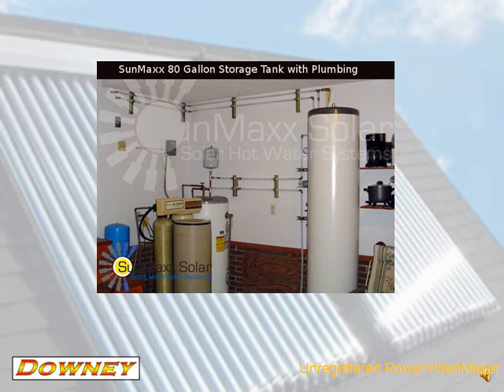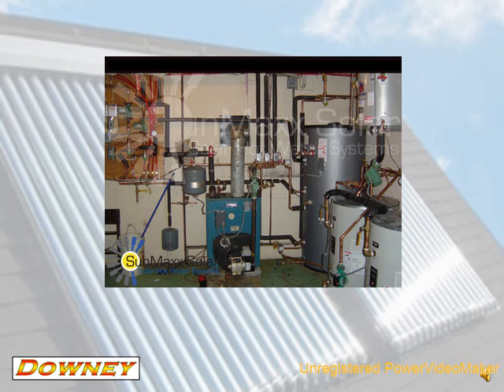Here's an example of a basic solar hot water heating system. On the right, you will notice an 80-gallon solar hot water storage tank. Now these tanks do differ from your typical hot water storage tank in that they're much more greatly insulated, and they have a heat exchanger that runs through the middle of the tank, where the heat transfer occurs from the heat in your collectors to heat your hot water. Here's an example of what it looks like to have a solar hot water heating system tied into your existing hot water boiler.